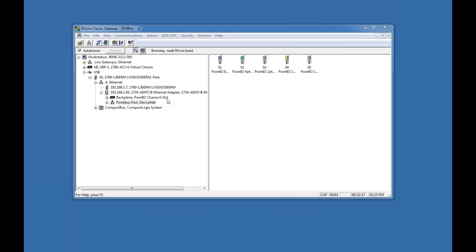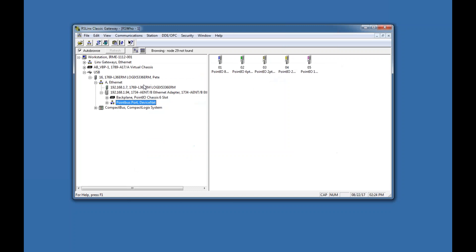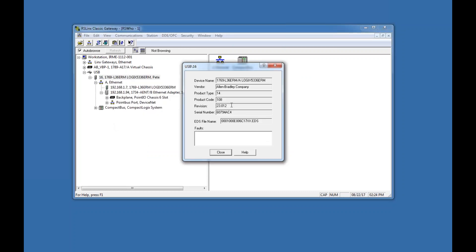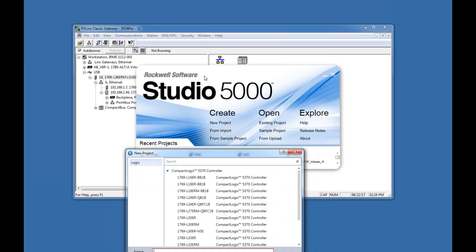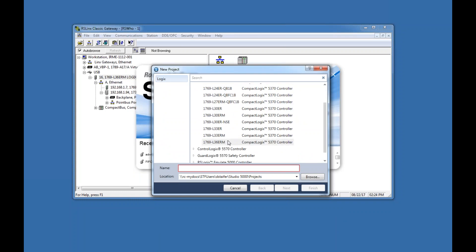Now I'm going to go into Studio 5000 and create a new program from scratch and add all the hardware. In Studio 5000, I need to create a new project. First, I go into RS Linx, right-click on the processor, and go to Device Properties. I can see I'm running Revision 23 — this is important. I also need to confirm I'm running an L36 ERM processor.